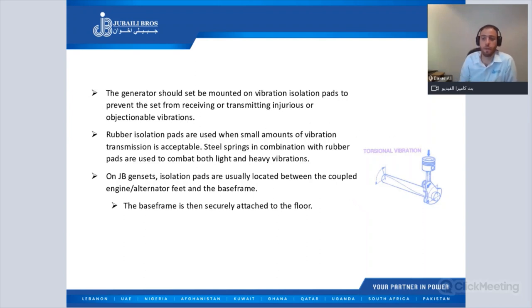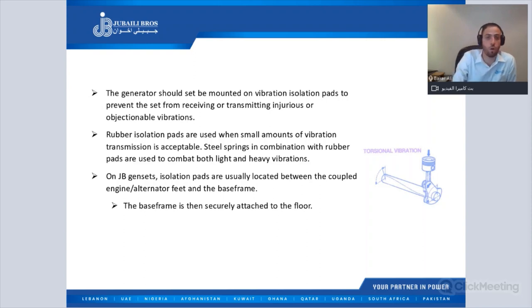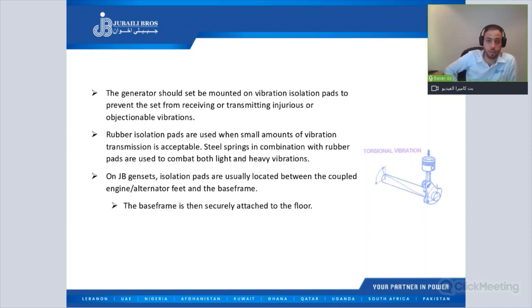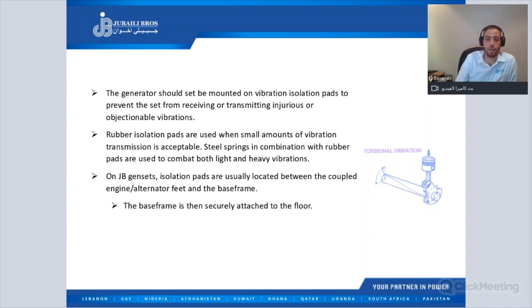Now we'll talk about generator mounting and anti-vibration. The generator should be mounted on vibration isolation to prevent the set from receiving or transmitting injurious or objectionable vibration. We have to install rubber mounting under the generator set before putting it inside the room. There are two types of anti-vibration isolation.